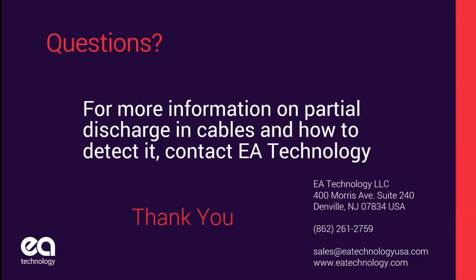Does the UltraTEV Plus 2 require calibration? Yes, it does. We calibrate in New Jersey. There are also calibrations in England, Singapore, and Australia, and we like to see it every year because it's handheld. It gets dropped. It gets bounced around. We like to see it once a year.